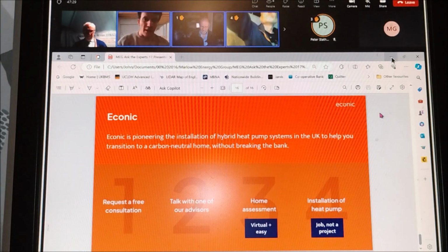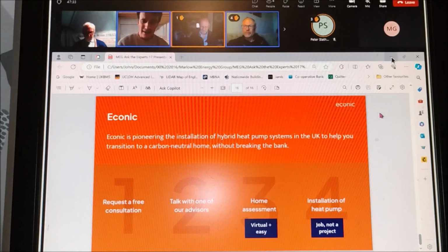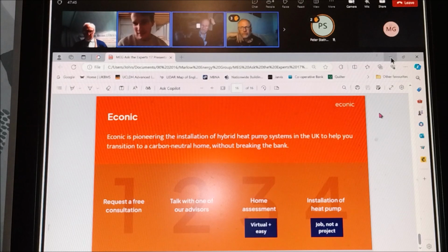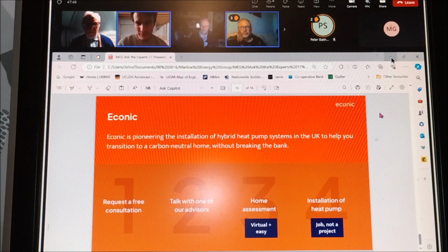But just important one, Bill. I think it is a little bit of a marketing gag, these high temperature heat pumps, because it's one of those things: while you can do it, you probably shouldn't. Almost exclusively the customers that we have are totally fine keeping the house warm at 55 degrees when it's -2, -3 degrees outside. So you don't have to go that high in terms of temperature.